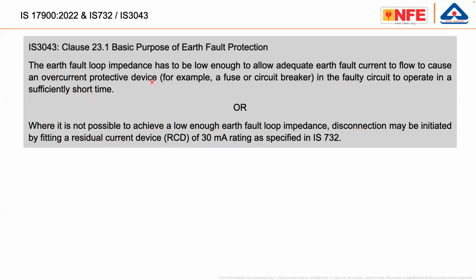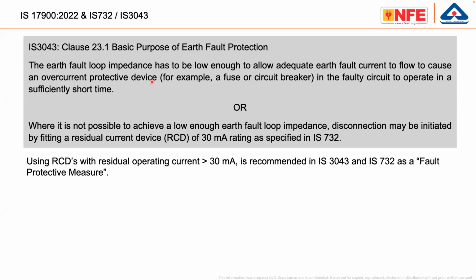So, fault protection can be achieved by disconnecting the supply, because one of the fault protective measures is automatic disconnection. For automatic disconnection, you can use an MCB or a fuse provided the fault loop impedance is low. If you cannot, then you should use an RCD. So IS 3043 and 732 have made the 30 milliampere RCD a fault protective measure. This is very careful to read. You should not confuse fault protection with additional protection. Using a 30 milliampere RCD for the lift car as an additional protective measure, you cannot compromise. Whereas what we are talking about here is fault protection. That means for the entire lift panel, if there is an earth fault, how to disconnect the supply is the subject.